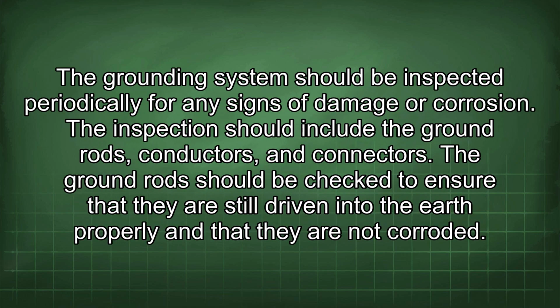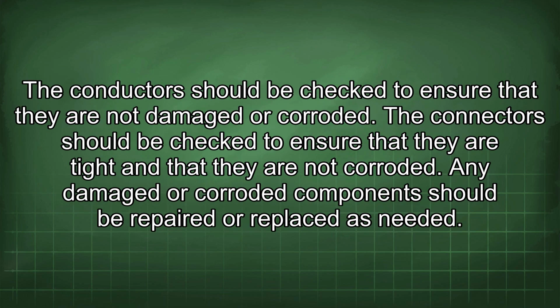The grounding system should be inspected periodically for any signs of damage or corrosion. The inspection should include the ground rods, conductors, and connectors. The ground rods should be checked to ensure that they are still driven into the earth properly and that they are not corroded. The conductors should be checked to ensure that they are not damaged or corroded. The connectors should be checked to ensure that they are tight and that they are not corroded.